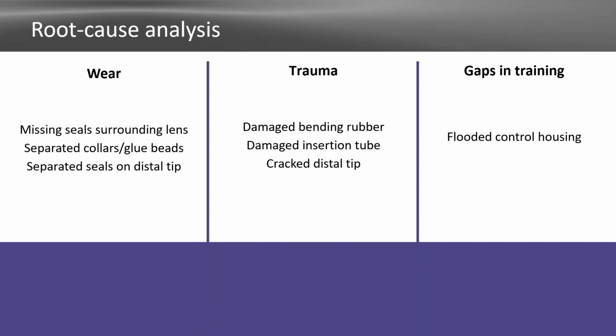So let's look at root cause analysis. For wear, the missing seals surrounding the lens, the separated collars, the glue beads, and then the seals on the distal tip, that is attributed to wear and tear. Trauma: bending rubber, damaged insertion tube, or cracked distal tip. That is all attributed to trauma. So the probe had some type of impact, some type of bite. It was dropped. I've seen probes slammed in doors.